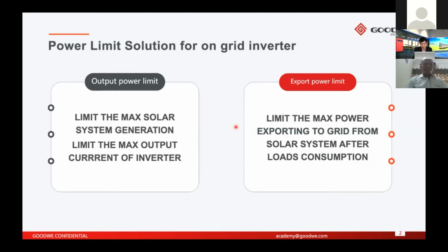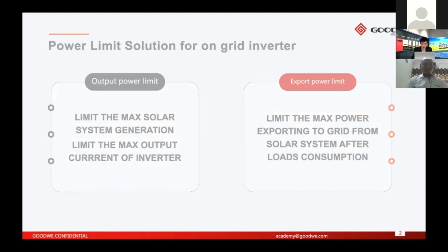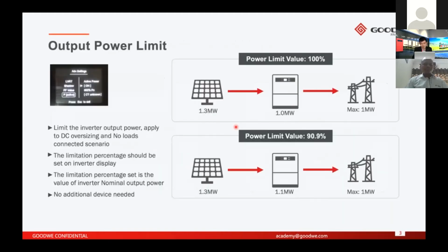So we split the power limit into two parts: output power limit and export power limit. Normally, the output power limit is applied to large systems, like commercial or utility scale systems. The export power limit is normally used for residential systems or small commercial rooftop systems. That's the export power limit application scenario. So let's check the details. First, I would like to introduce the output power limit. You can find the diagram here.